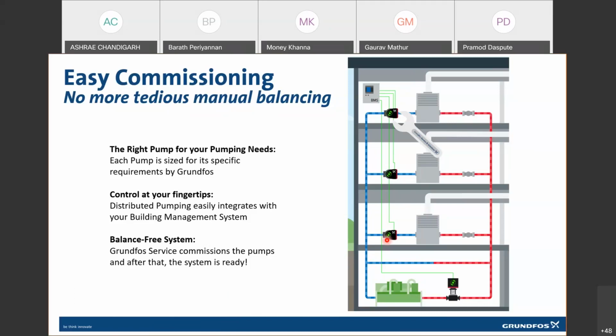What I mean is we have the right pump for the right pumping need. The pump in the production loop is designed for the loop on the production side. So with the help of these arrows, you can understand that the pump in the production loop, the primary chilled water pump, has reduced drastically in size. This is what I mean by the right pump for the right pumping needs. And this is the one change you see: there is a reduction in the size of the primary chilled water pump depending upon your production loop friction losses. So this is the loop based on which your primary pump is designed.